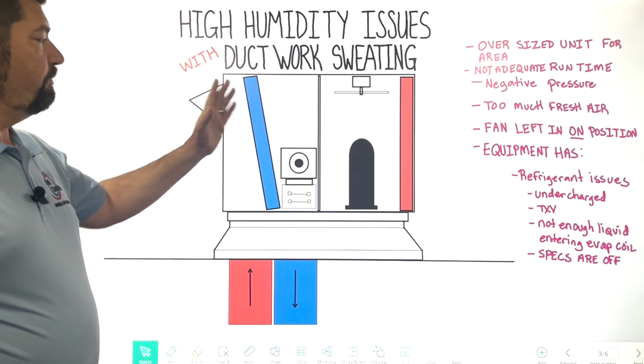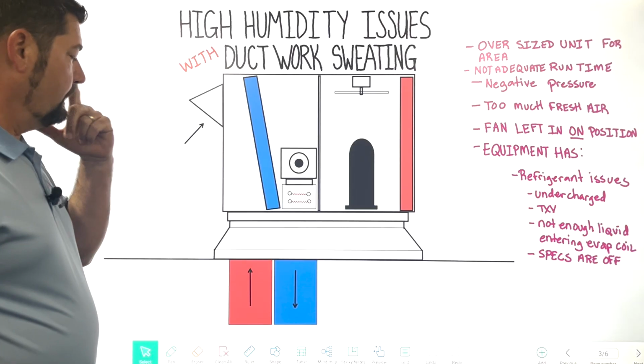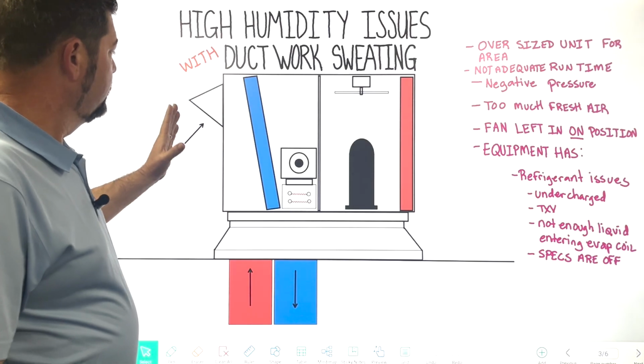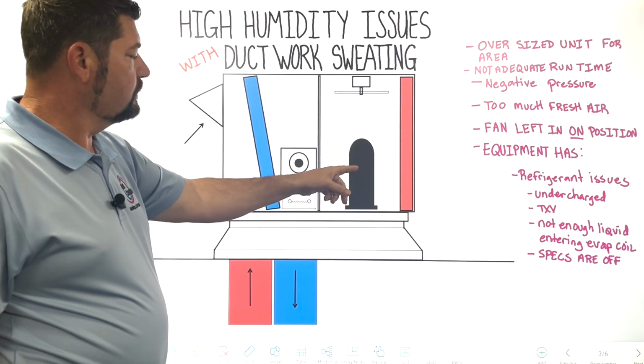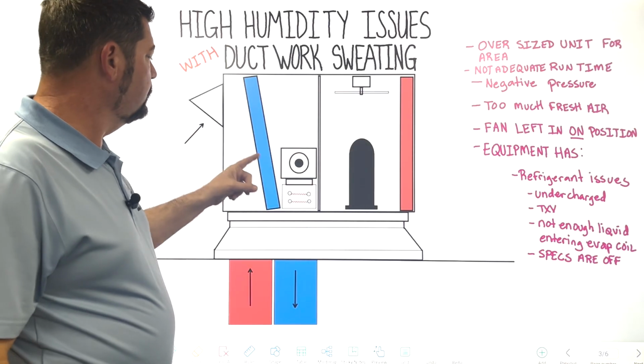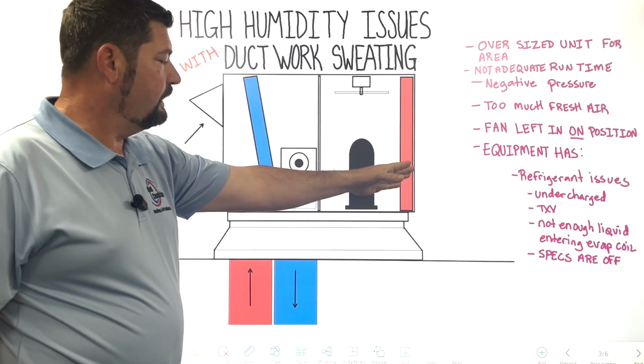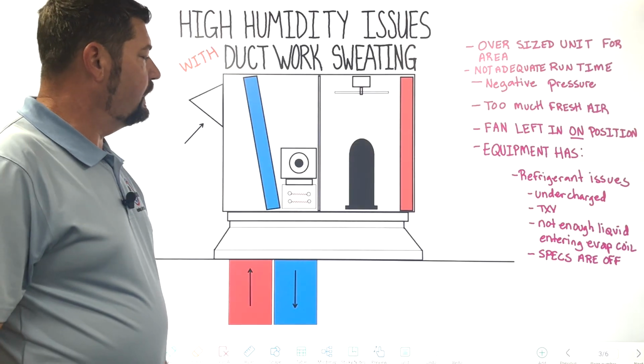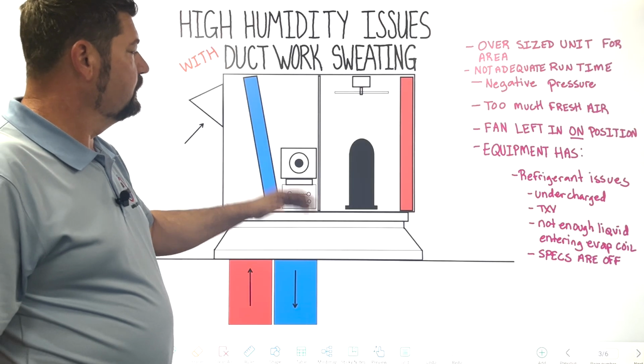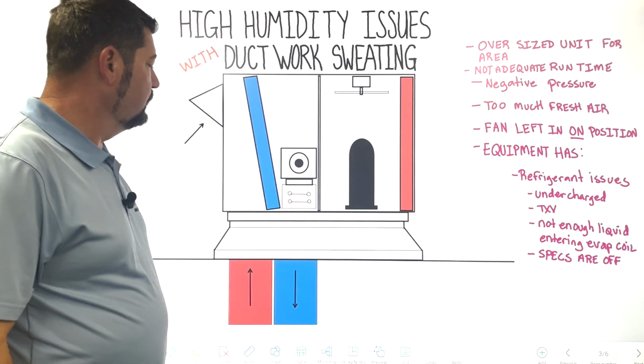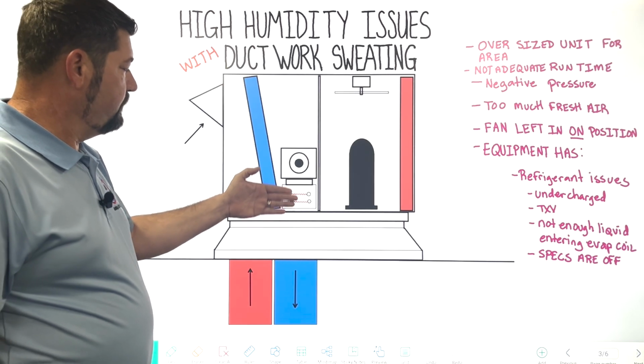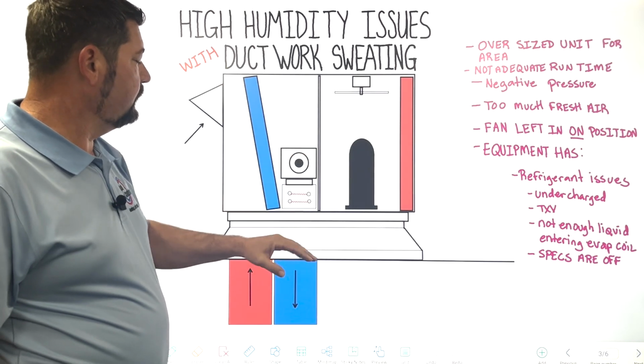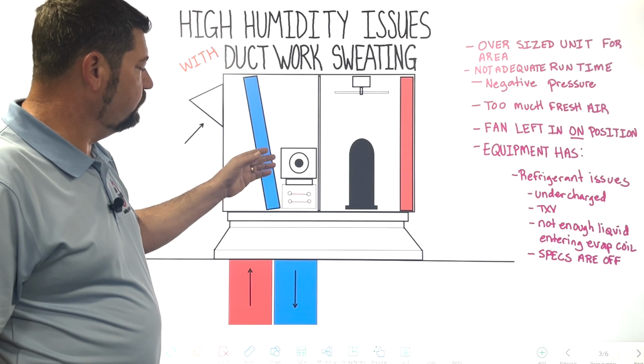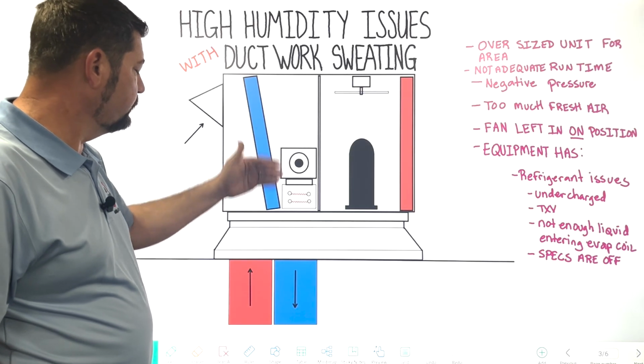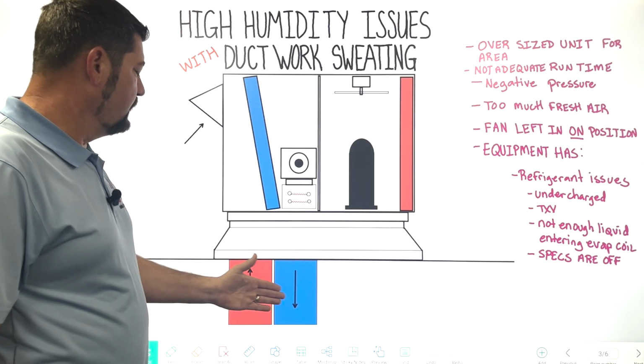Okay, getting right into it. I have a drawing of a rooftop package unit. We call them an RTU. Let's go ahead and go over the drawing. We have the unit itself. We got a condenser fan motor, a compressor, a condenser coil, an evaporator coil. It's obviously in cooling because the outdoor coil is in a high pressure. The indoor coil is in a low pressure, indicating cool gas, hot gas. I put some heat strips there just underneath the blower. Not that that's going to be relevant to today's lesson, but just to put that in there. Why not? And obviously, this would be my version of direct drive. There's no belts here. We have a return air plenum and a supply air plenum.